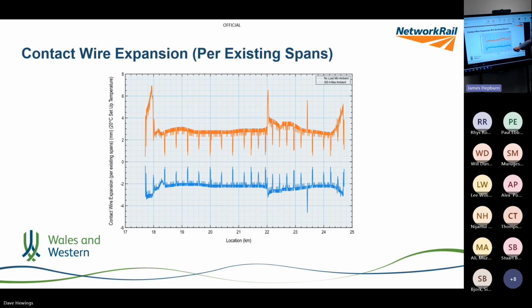So we can look at how much the whole thing moves based on that - you can see there the overlaps even, there are structures much closer together. You see those spikes where there's much less movement. That's the amount of expansion in millimeters based on a 20-degree set up temperature and that temperature range. So as a first pass, with broad assumptions we've set out, that allows us to say, if that's happening on a span-by-span basis, what would happen if we added them all up?